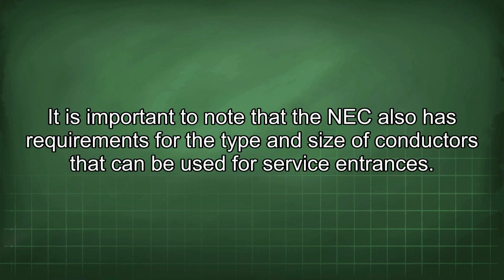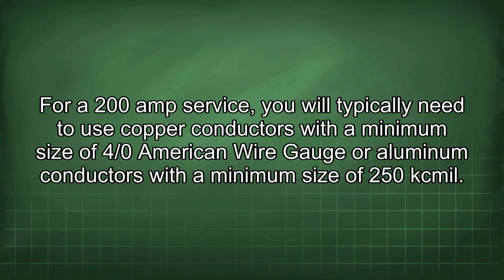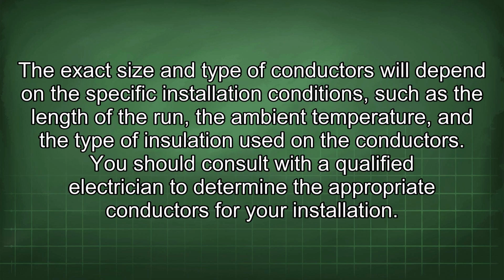It is important to note that the NEC also has requirements for the type and size of conductors that can be used for service entrances. For a 200 amp service, you will typically need to use copper conductors with a minimum size of 4/0 American wire gauge or aluminum conductors with a minimum size of 250 kcmil. The exact size and type of conductors will depend on the specific installation conditions, such as the length of the run, the ambient temperature, and the type of insulation used in the conductors. You should consult with a qualified electrician to determine the appropriate conductors for your installation.